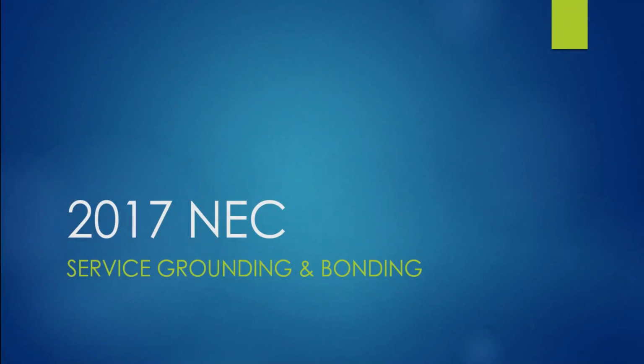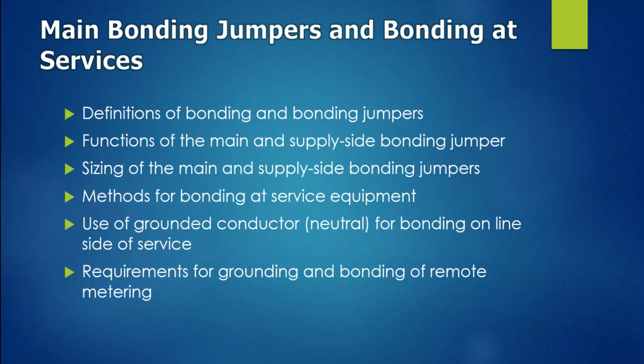And while we do that, we'll also get into remote meter bonding and what you have to do there, remembering that it is still service conductors going from a remote meter, or even a meter disconnect, onto the service equipment. All of those things have to be taken into consideration, and we're going to look at them during this presentation. So let's get right into the PowerPoint presentation. Again, this is the 2017 NEC. We will reference earlier editions where necessary, but for this case, we're going to deal with the 2017 NEC.